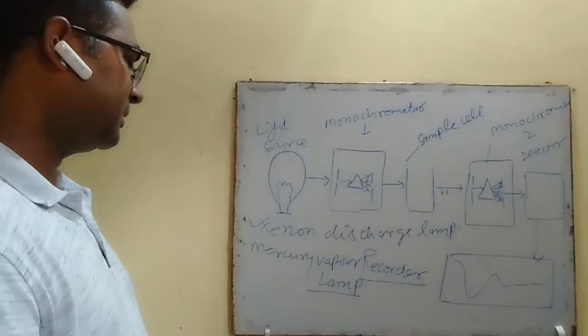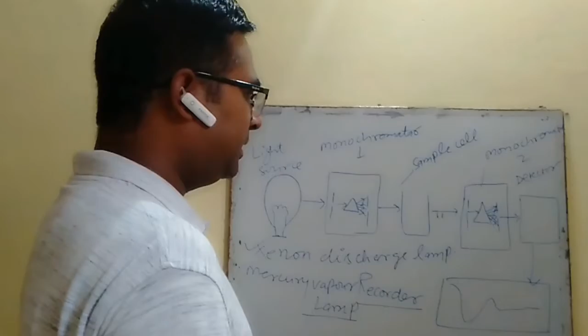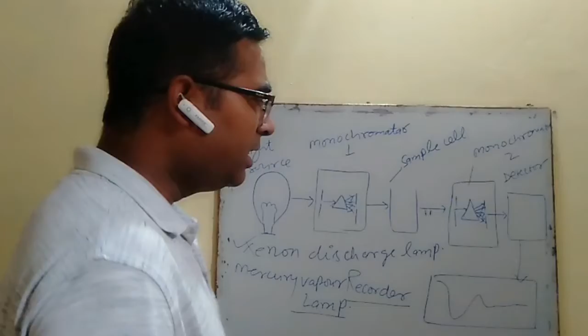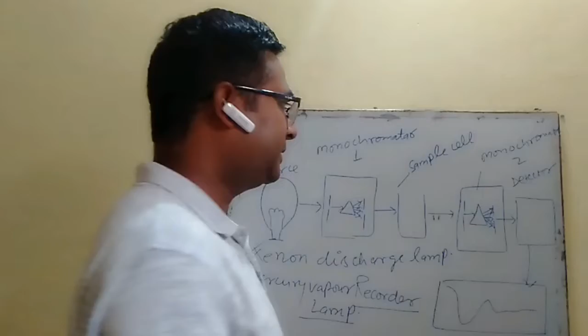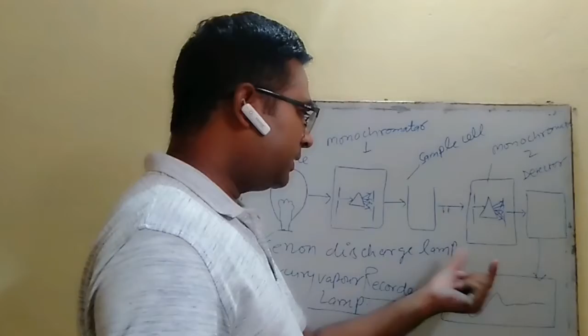When our objective is to determine the emission spectra, monochromator 1 may be used as a simple filter. A simple filter may be used in place of the prism and grating system generally used in a monochromator. But if we have to record the excitation spectra, we must use the grating system or prism in monochromator 1. The detector generally used in a spectrofluorimeter is a high sensitivity photomultiplier tube, because the intensity of light emitted by most samples is very low. So the sensitivity of the detector must be high, and the signal generated by the photomultiplier tube is amplified and finally sent to the recorder, which records the spectra. So this is the basic schematic diagram of the spectrofluorimeter.